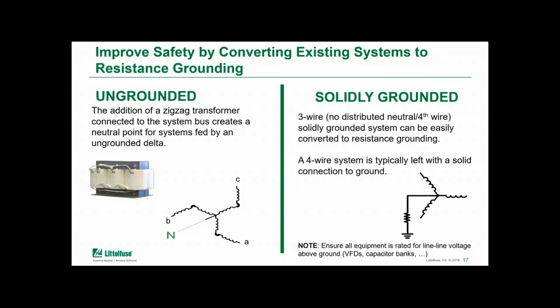Now it's done using a zigzag transformer as shown on the slide. And this zigzag transformer is connected to the bus, which creates a neutral point that can be resistance grounded. And a 3-wire solidly grounded system can also be converted to resistance grounding. And in this case, you would typically just connect a resistor directly between the X0 and ground. And when I say resistor, I mean it is a purpose-built grounding resistor. It's not something you can just pull the toaster from home and wire it up.